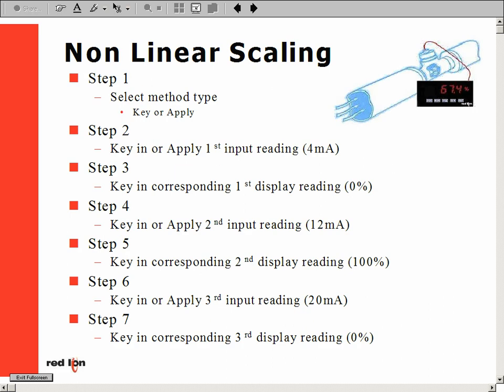In step 4, we key in or apply our second point input value. In our example, we would enter 12 milliamps. The next step has us key in the appropriate display value corresponding to our mid-way point — in our example, that is 100%. Step 6 has us key in or apply our high point input signal, or 20 milliamps. The final step is programming the corresponding display value, which is 0%.